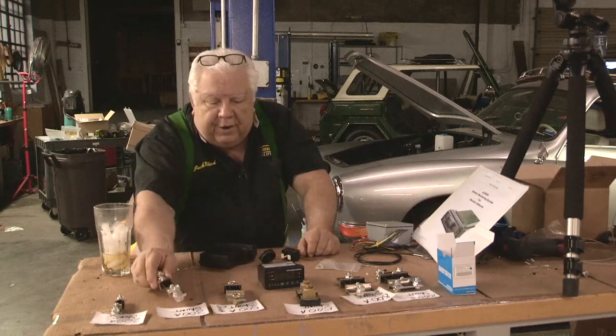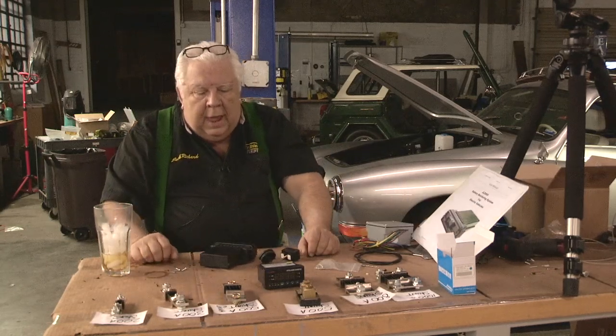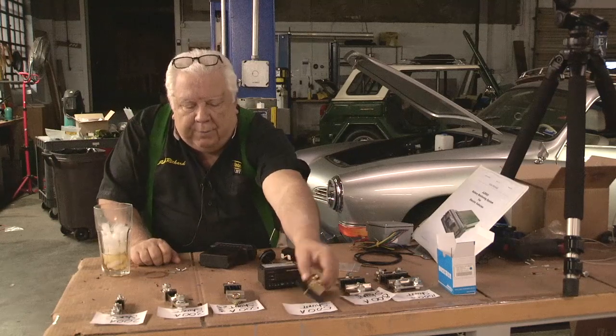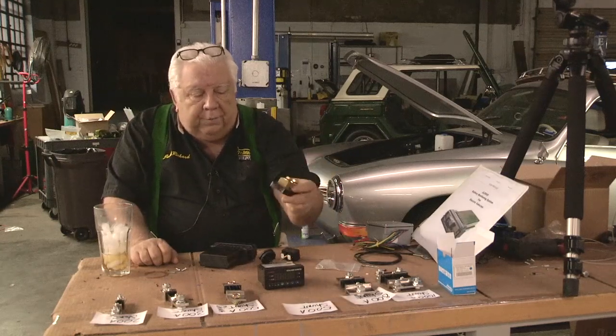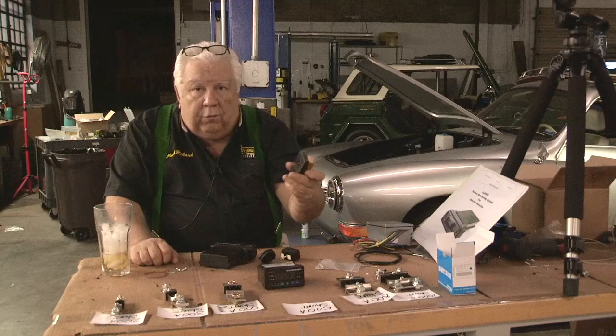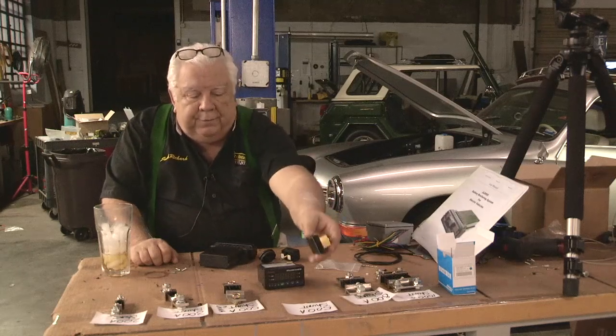This one will likewise read 75 millivolts at 1,000 amps, whereas this one down here is a 300 amp, 75 millivolt shunt. And this is a 500 amp, 50 millivolt shunt, it'll read 50 millivolts at 500 amps.